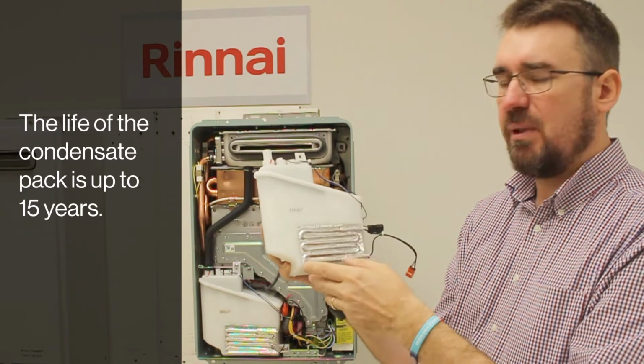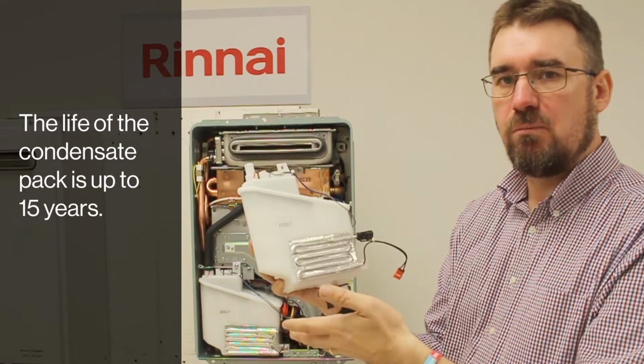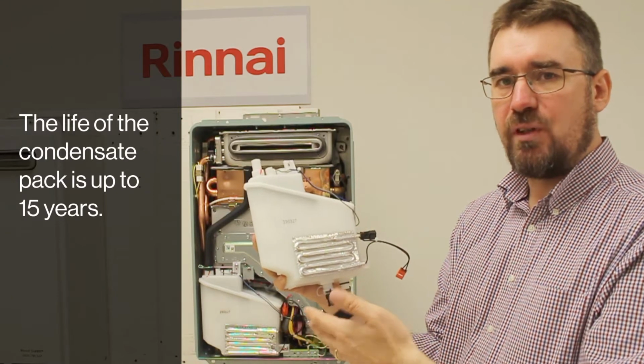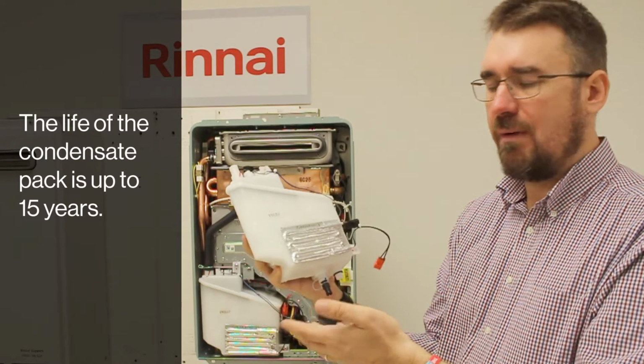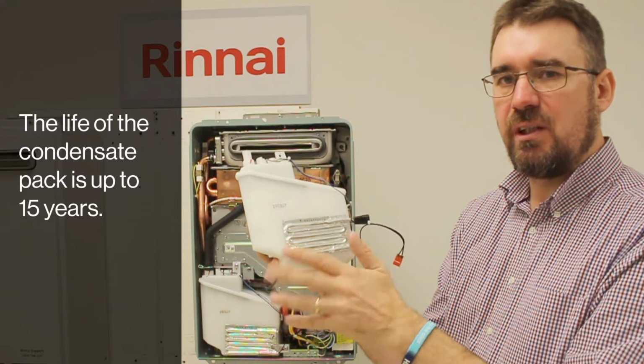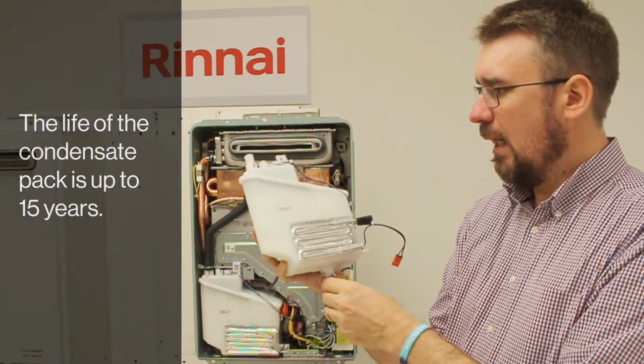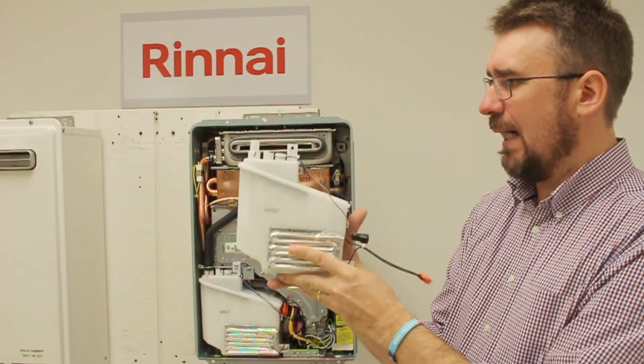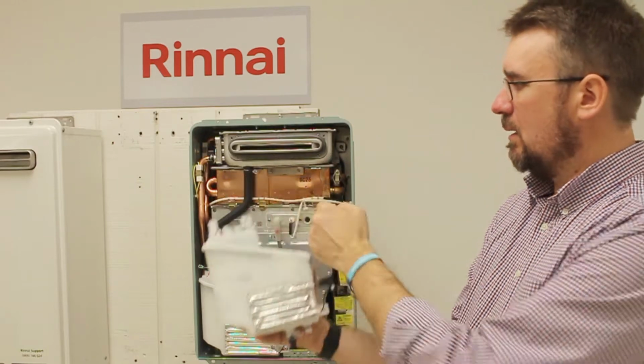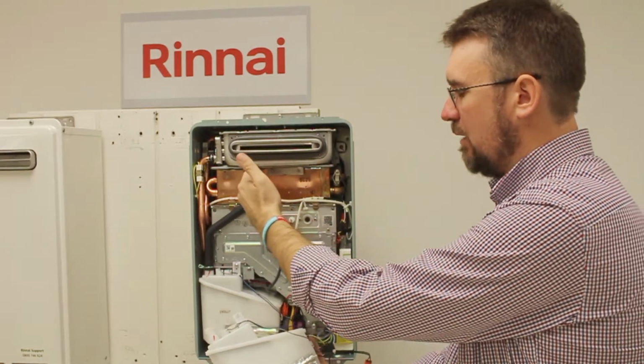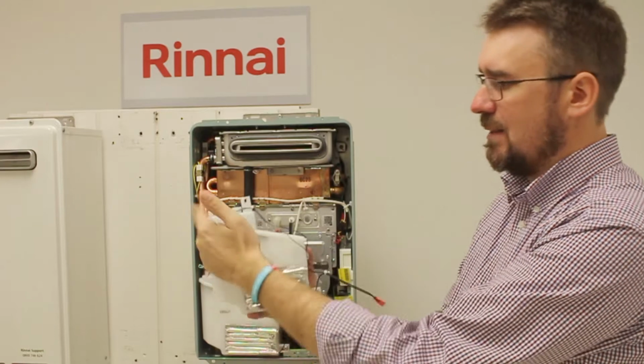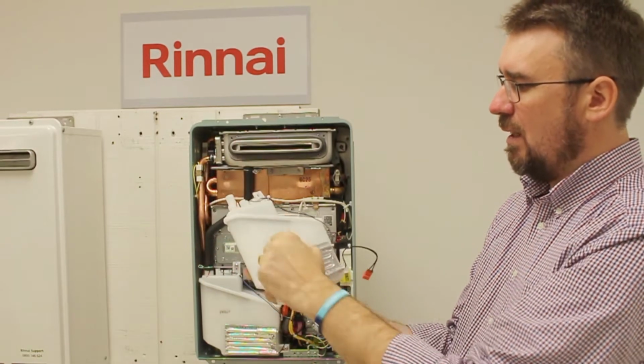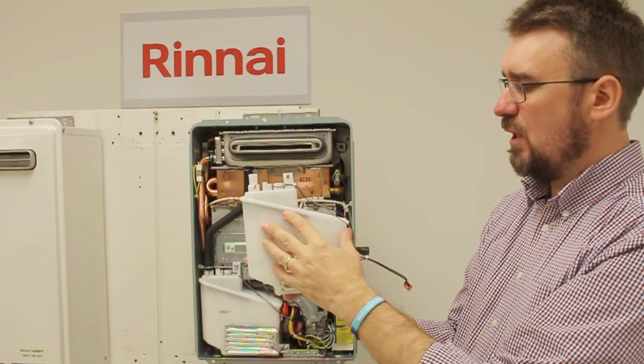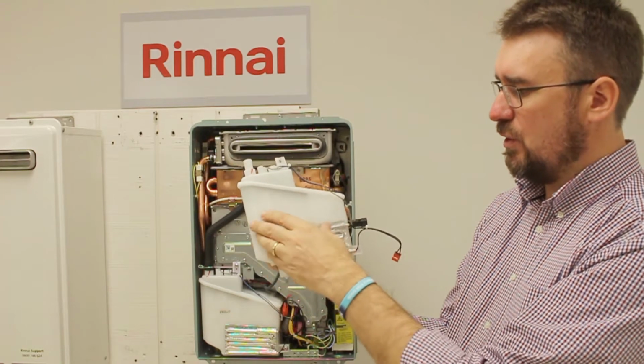There's a bit of a caveat there: it may wear out quicker if the unit has much higher running hours, but broadly 15 years of normal domestic use. Okay, so a bit of a tour around the pack then. The condensate comes out of the secondary heat exchanger and down into the pack, entering here. What we've got inside here is fundamentally lime chips. They react with the condensate to neutralize it.